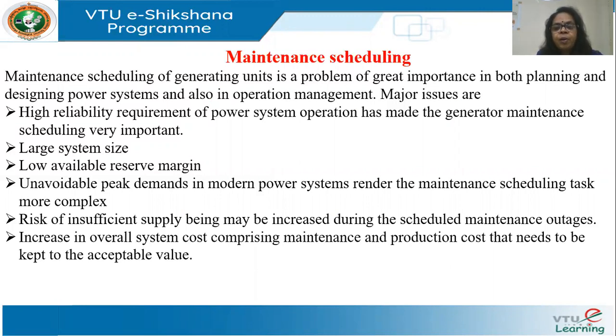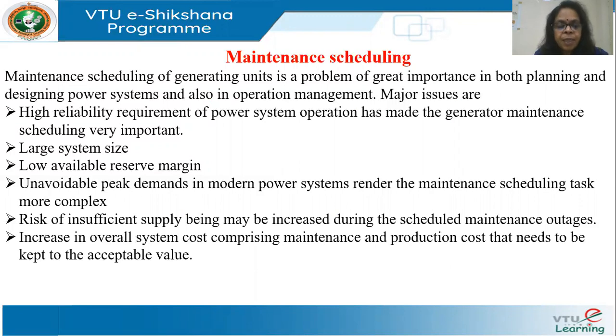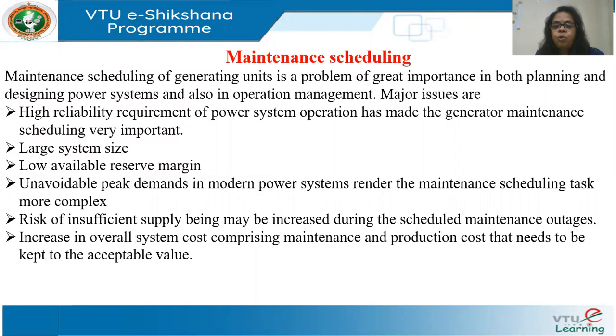Some major issues include the high reliability requirement of power system operation. When a generator is removed for maintenance, you have to make alternative arrangements, so some redundancy has to be there in the system. Another major challenge is the large size of modern grids. Modern grids are really large and that has an impact on scheduling, and normally because of cost constraints we operate with low reserve margins. This creates problems when equipment is outaged or removed for service.